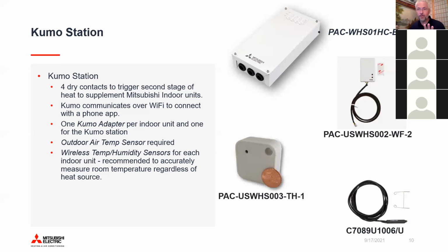And so the illustration of that is, if you didn't have this sensor and you were sensing the temperature of the room from the wall mount unit, and your baseboard on the other side of the room comes on as a backup, well, you might cook the other side of the room by the time your heat pump realizes what the temperature of the room is. So by being able to have that remote sensor and park it where it's balanced to measure an appropriate room temperature where it's going to be comfortable for people, you'll get the best of both worlds.